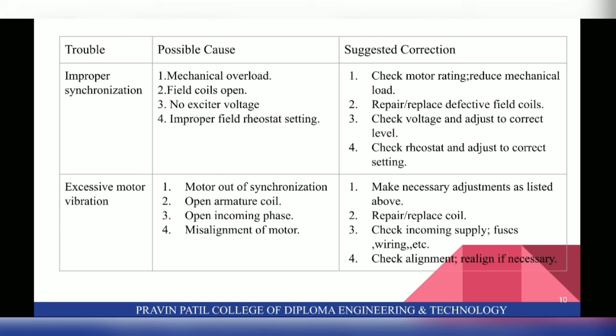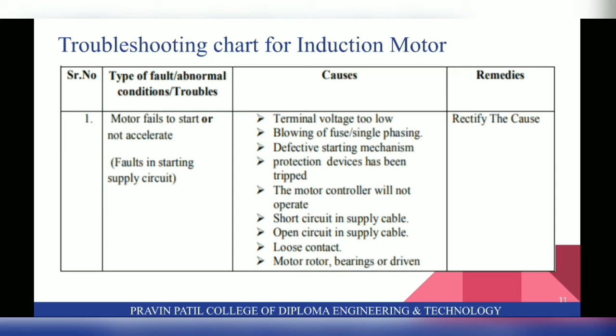A possible cause for this fault is terminal voltage too low, blowing off fuse or single phasing, defective starting mechanism, protection devices have been tripped, the motor controller will not operate, short circuit in supply cable, open circuit in supply cable, loose contact, motor rotor, bearing or driven load is locked, overloaded, bearing is seized or frozen.